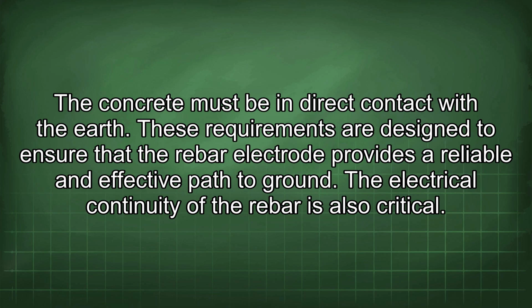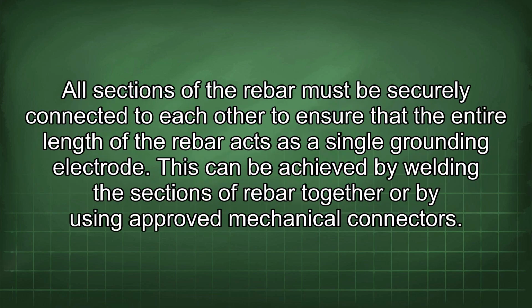The electrical continuity of the rebar is also critical. All sections of the rebar must be securely connected to each other to ensure that the entire length of the rebar acts as a single grounding electrode. This can be achieved by welding the sections of rebar together or by using approved mechanical connectors.